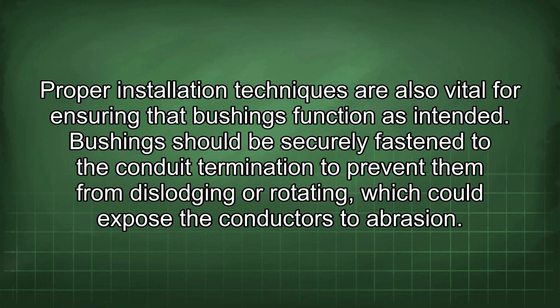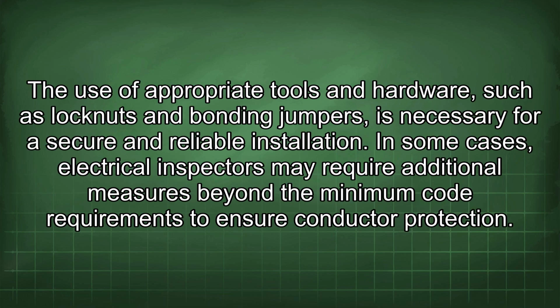Proper installation techniques are also vital for ensuring that bushings function as intended. Bushings should be securely fastened to the conduit termination to prevent them from dislodging or rotating, which could expose the conductors to abrasion. The use of appropriate tools and hardware, such as lock nuts and bonding jumpers, is necessary for secure and reliable installation.